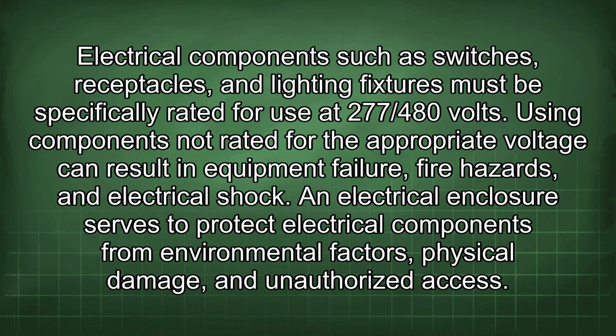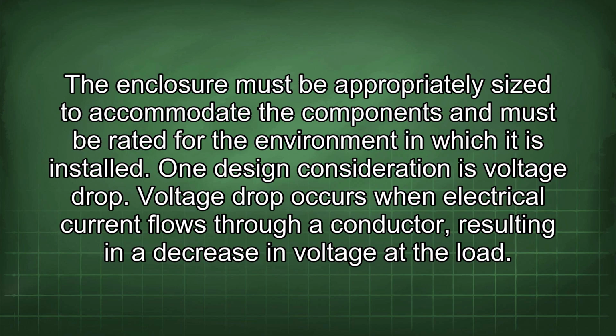Electrical components such as switches, receptacles, and lighting fixtures must be specifically rated for use at 277/480 volts. Using components not rated for the appropriate voltage can result in equipment failure, fire hazards, and electrical shock. An electrical enclosure serves to protect electrical components from environmental factors, physical damage, and unauthorized access. The enclosure must be appropriately sized to accommodate the components and must be rated for the environment in which it is installed. One design consideration is voltage drop.